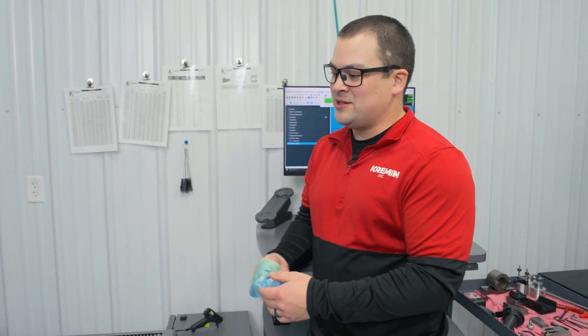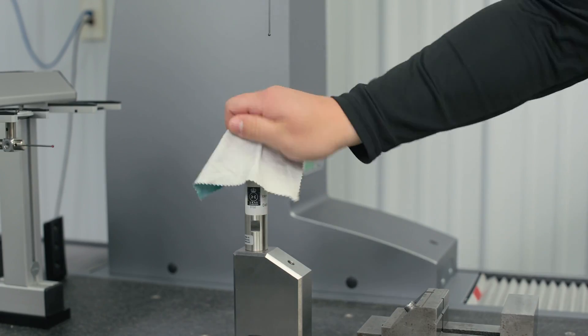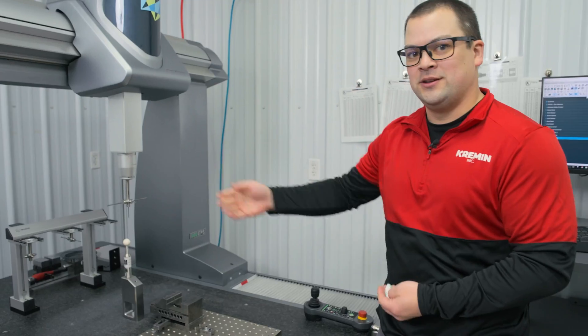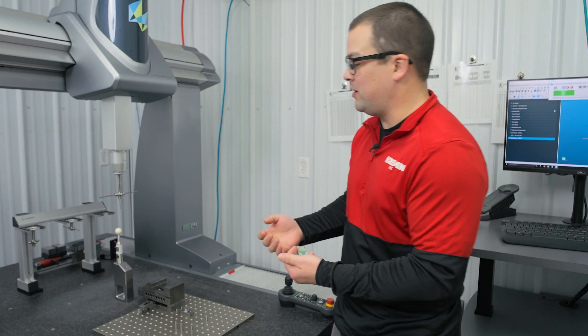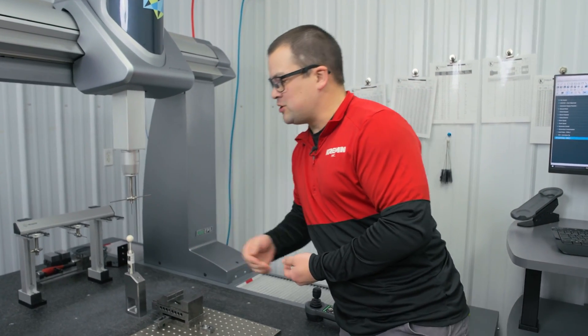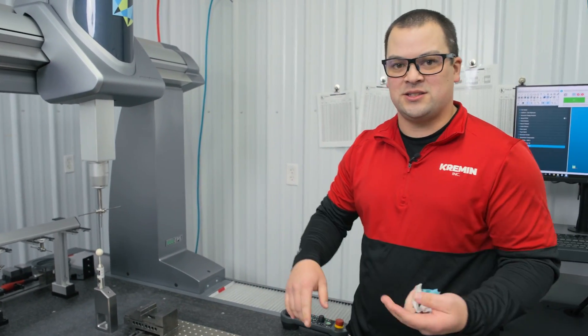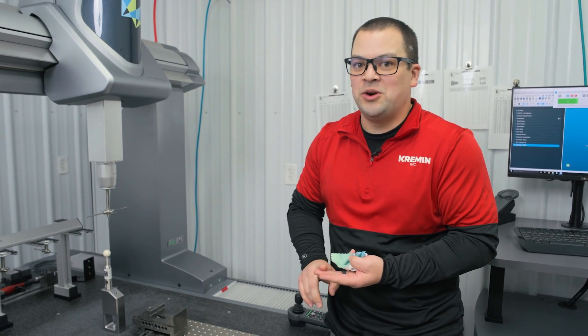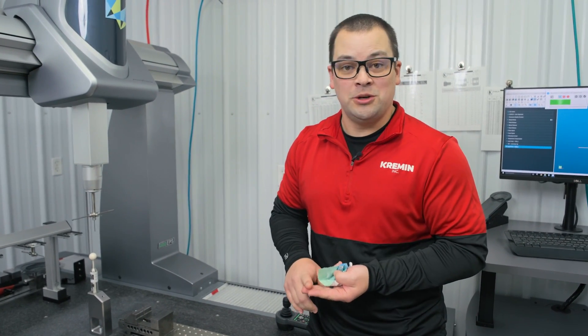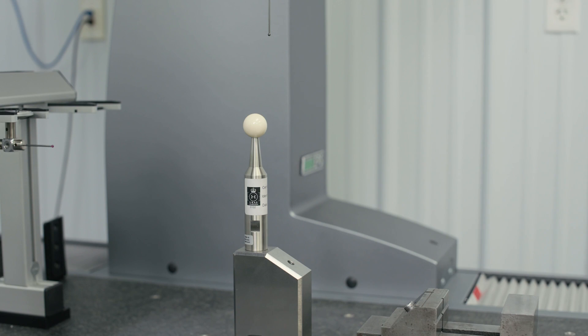One thing to remember is to make sure that your calibration sphere and your probes are clean so you can get the most accurate data you can when you qualify these, calibrate them. Visually inspect your probes, make sure there's no dust, no metal chips, nothing that you don't want on the probes. Clean those off, clean off your sphere, you're good to go.